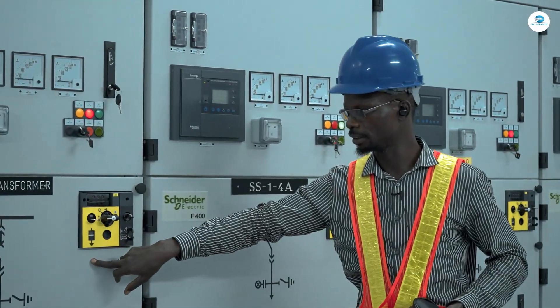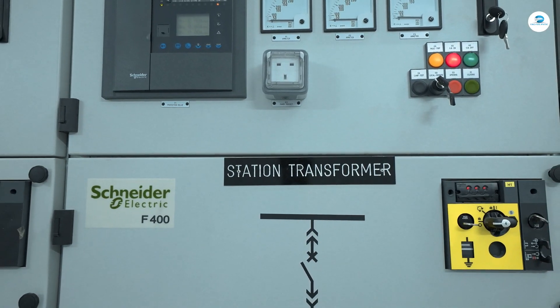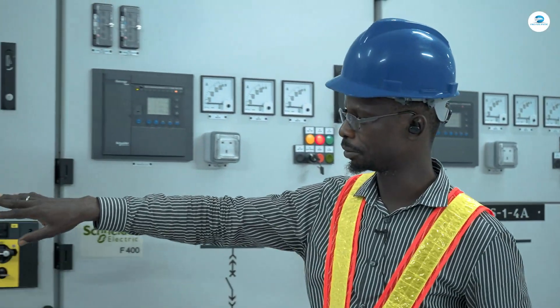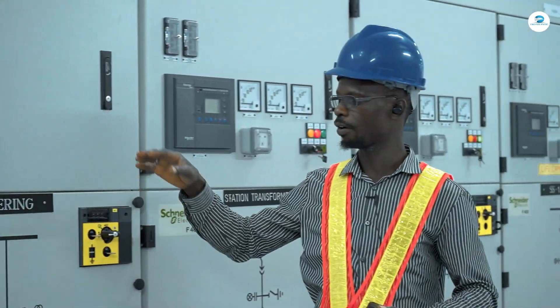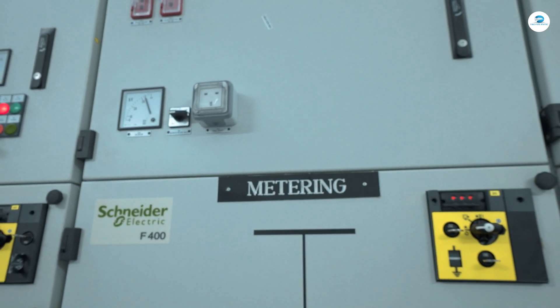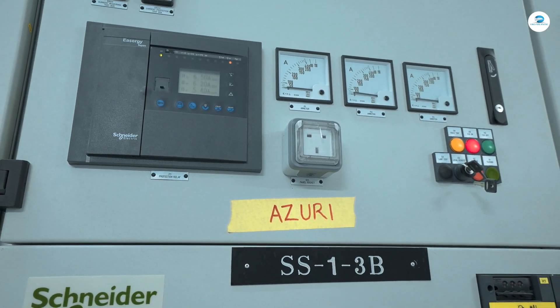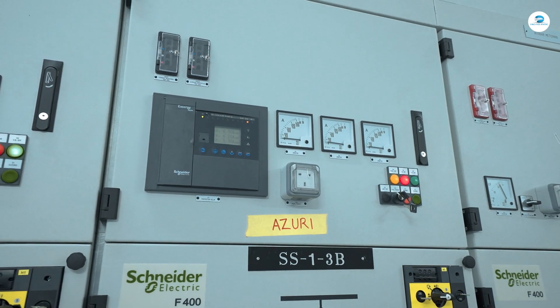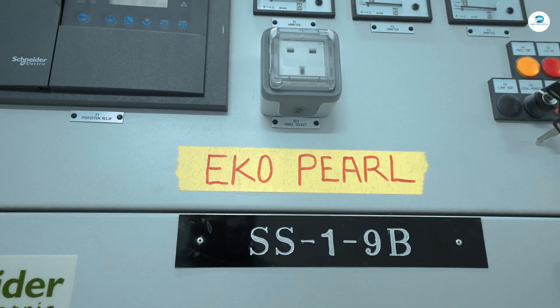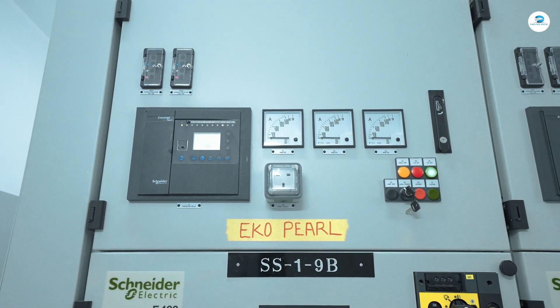The next one here is the station transformer. This station also has a transformer that steps down from 33,000V to 400V for use within this facility. After this, we have the metering panel, which meters all the energy going out to see exactly how much energy is being supplied to the customers. The next panel is for Azuri — feeding Azuri 33,000V, and they also have a transformer there that steps it down from 33,000V to 400V. Likewise, we also have an Eko Pearl panel that does the same: 33,000V to their end, stepped down to 400V using a transformer.